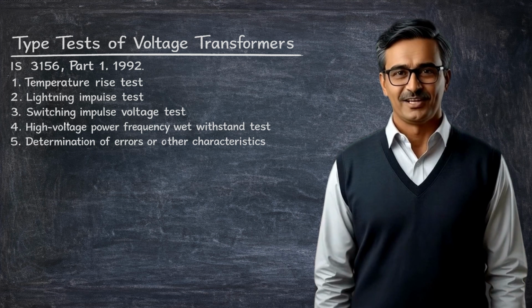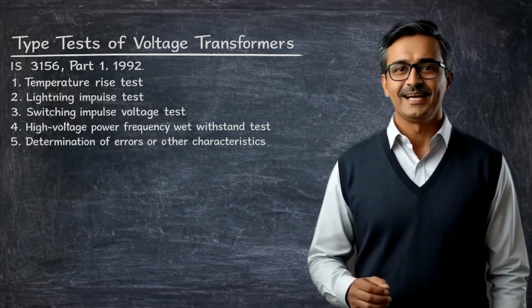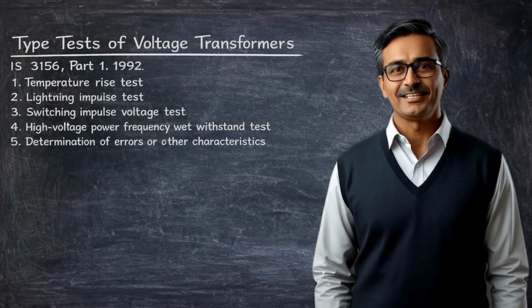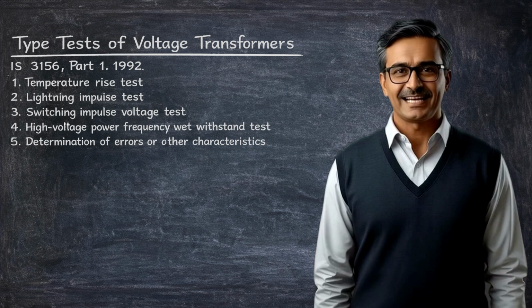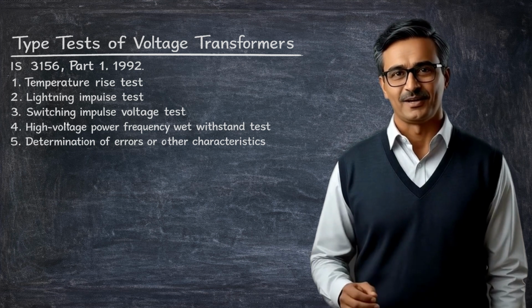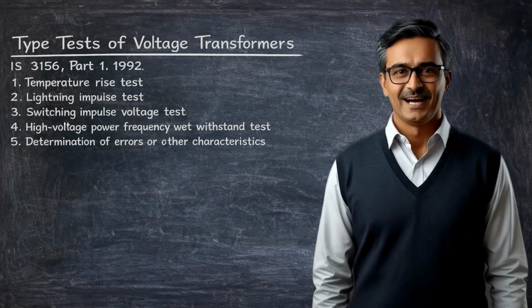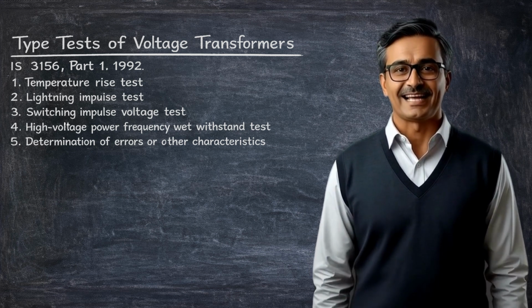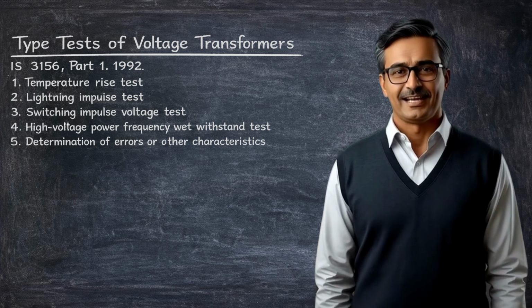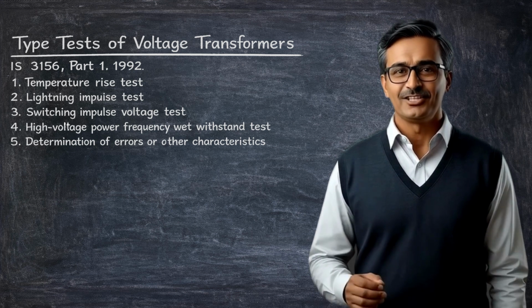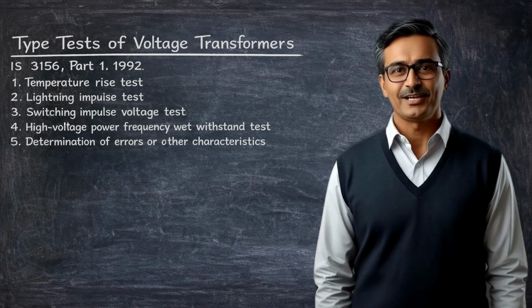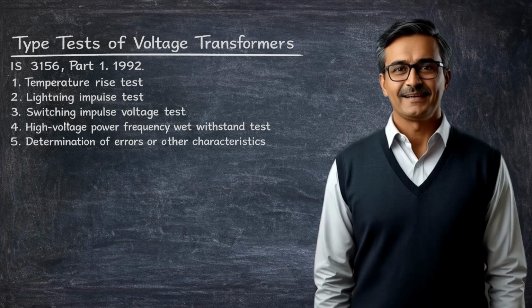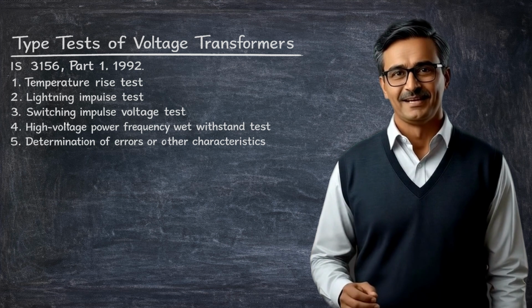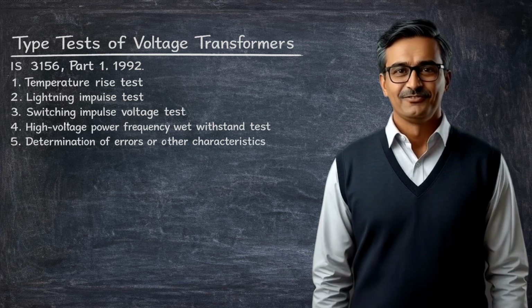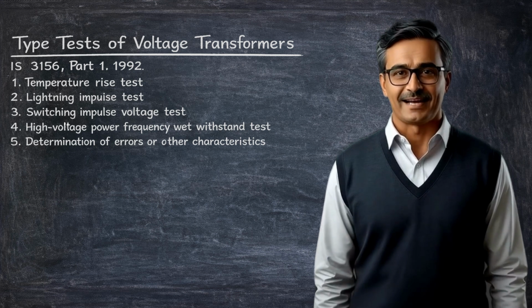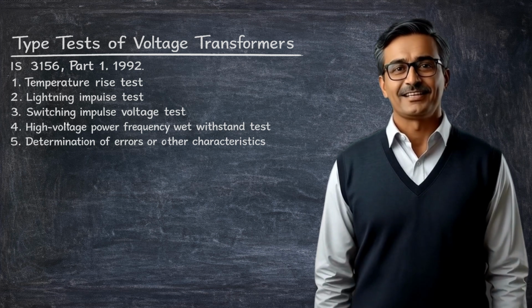Now let us look at some important notes related to type testing. First, the dielectric type tests, which include the lightning impulse test, switching impulse test, and wet withstand test, should normally be carried out on the same transformer unless the manufacturer and purchaser agree otherwise. Second, after completing these dielectric type tests, the transformer must be subjected to all the routine tests again. This ensures that the transformer has not been damaged during the high voltage testing process. Finally, type tests may be omitted in certain cases. If the manufacturer already has a valid certificate of type tests conducted on a similar transformer and the purchaser accepts it, then repeating the type tests may not be necessary.